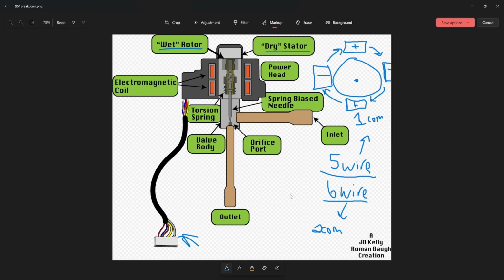So I mentioned the 6 wires that Trane uses. They have brown and red as your commons, and you have certain colored wires or certain coils you need to check to each common. Brown always gets tested to blue and yellow for Trane. So you check the resistance, or your ohms, of blue to brown and yellow to brown, and red always goes to orange and white for the 6-wire EEVs. So you would go red to orange, red to white.